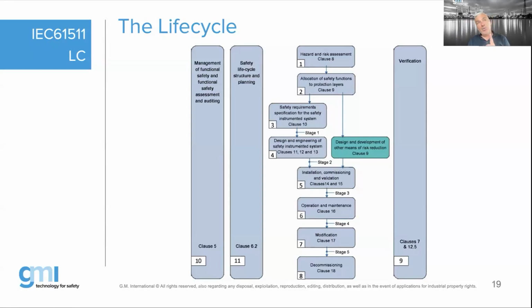But the standard is quite cleverly written, in the sense that it's not only good enough to say we have a second name, person A programmed, person B has verified, and person B said, looks okay. The standard is asking person B, the four-eyes principle, to prove how did you decide that the logic program by person A, its functionality, is correct. How did you do that? And that's completely, of course, different than just having a second name.